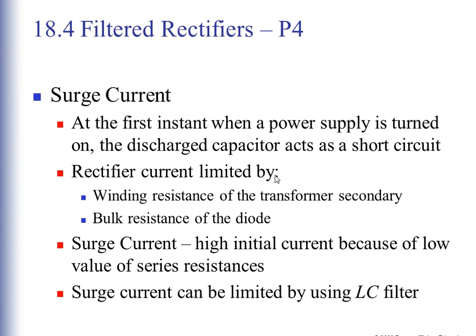I discharge the capacitor for a little bit. The rectifier current is limited by the windings of the transformer itself. My transformer is rated for, say, 1 kilowatt—I can't get any more than that through the transformer. In fact, if I ground the secondary of a transformer, that ground isn't seen on the primary side. All it does is provide whatever the rating of the transformer is to ground, and it won't care, because it's a magnetic coupling from one side to the other—I can't make the magnetics move any quicker. I can only transmit whatever the full load of the transformer allows; that's as much as I can get out of it.